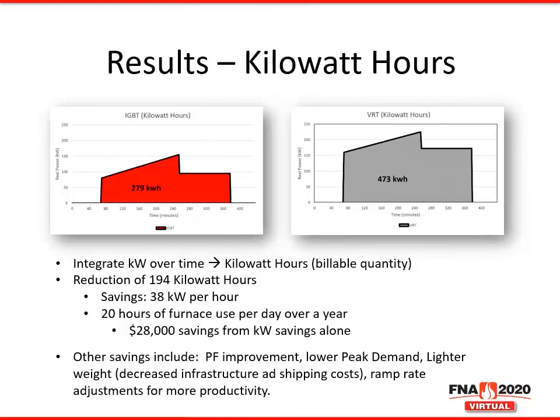In this slide, we're going to look at kilowatt usage more closely. These graphs are similar to the first graph I showed you, where the left y-axis is kilowatt usage, and the x-axis on the bottom is total time. If you integrate the kilowatts used over time, you get to the billable quantity of kilowatt hours. The difference between the VRT and the IGBT MFDC system was approximately 194 kilowatt hours. This equates to a savings of 38 kilowatts per hour of use for this furnace.